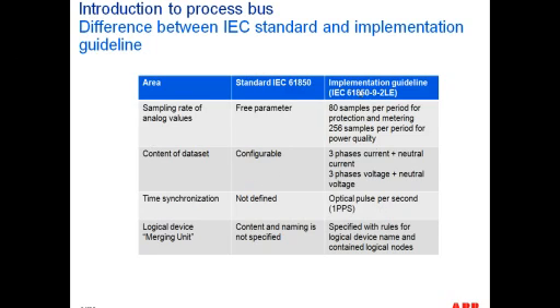Another topic that was up for discussion and not really defined inside 61850 was the source of time synchronization. And what the 9-2 LE implementation guidelines prescribed is the utilization of optical pulse per second, or 1 PPS, as the standard time reference for a sampled measured values implementation. And then the other essential definition inside the implementation guidelines was the definition of the logical device merging unit, where now inside the implementation guidelines there are specific rules for the logical device name and contained logical nodes. And this is obviously important from an engineering perspective.